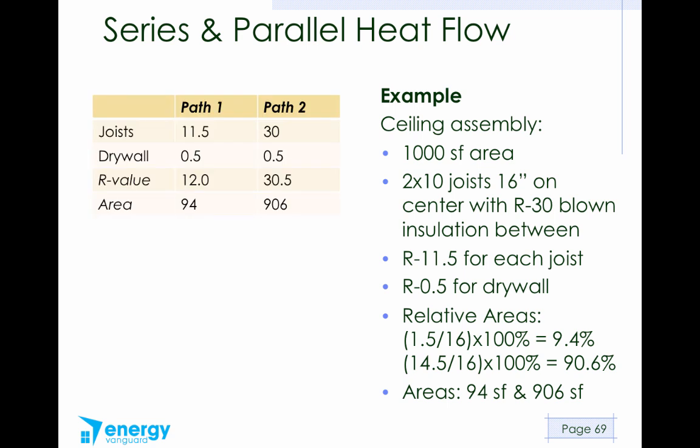All right, let's work through this now. So the first thing is we've got two pathways. We've got the pathway where the heat travels through the ceiling joists and then the drywall. That is what we're calling path 1. And we've got the pathway where the heat travels through the insulation and then the drywall. That's path 2. If it goes through the ceiling joists, the R value it encounters is 11.5 through the wood, and then 0.5 in the drywall.